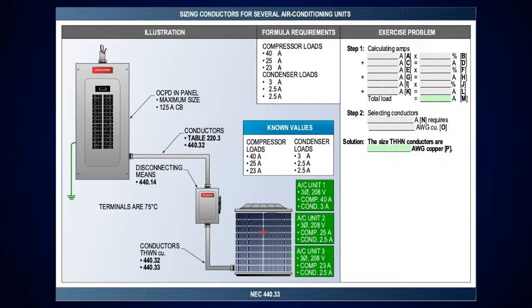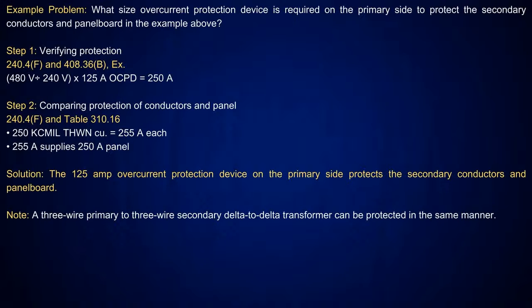So in this one, looking at AC units 1, 2, and 3, the largest is the 40 amp. Then everything else is at 100%. Get your total amperage and size your conductor going over there to tap off of that to feed each one of those.